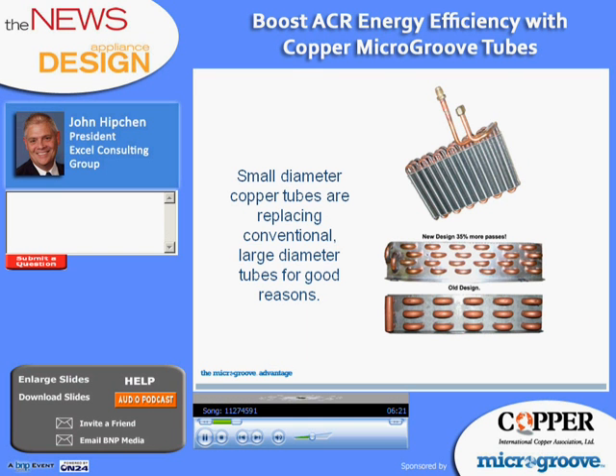In this photo, the manufacturer advertises 35% more passes, and that's important because it translates to higher heat transfer, higher efficiency, less material is used to make the coil, and in many situations it also means less energy is used in the system. Note that in the new coil, the tubes are arranged in a staggered pattern, and we will see in this presentation how that can make a significant difference in the performance.